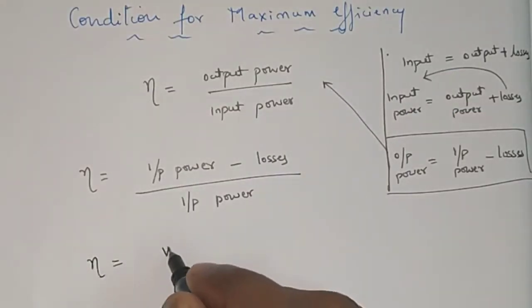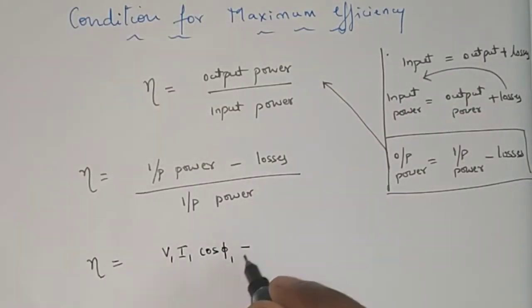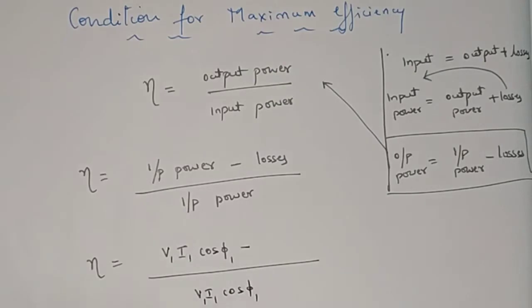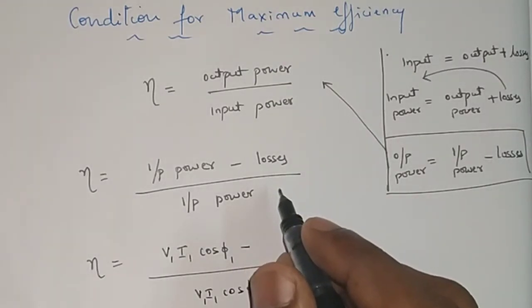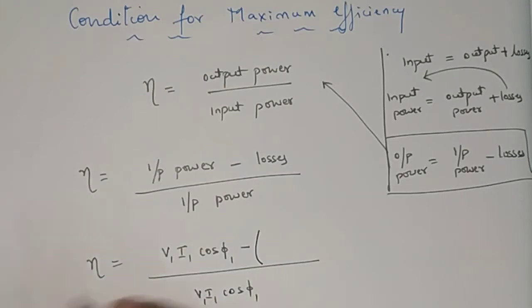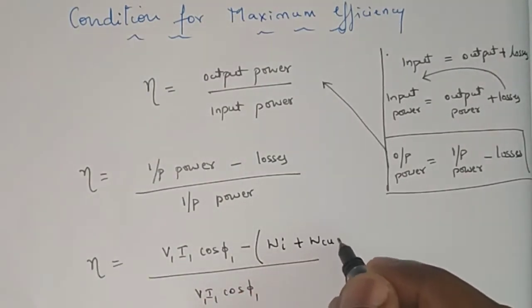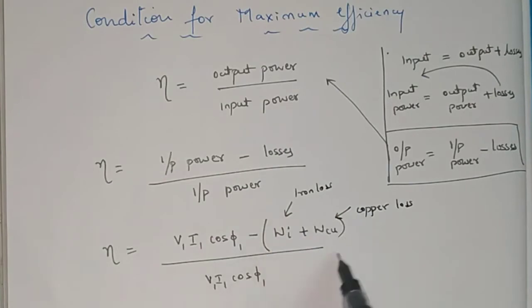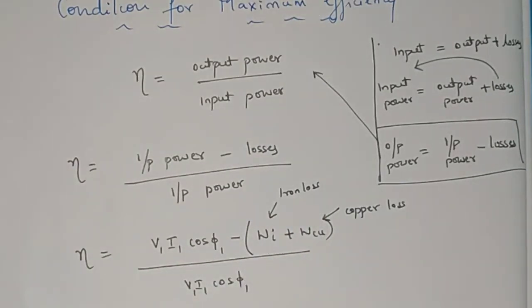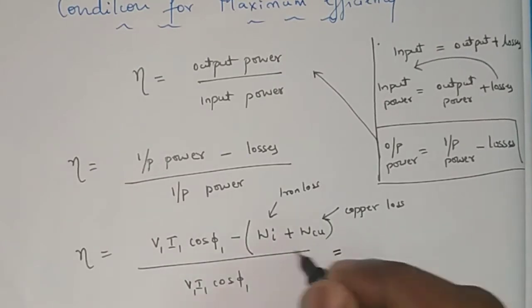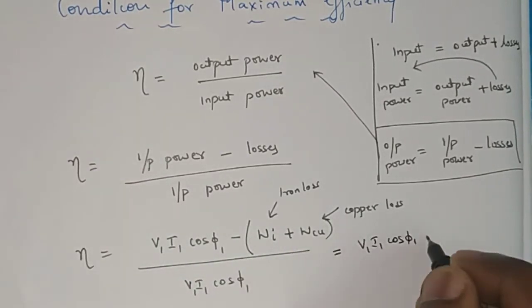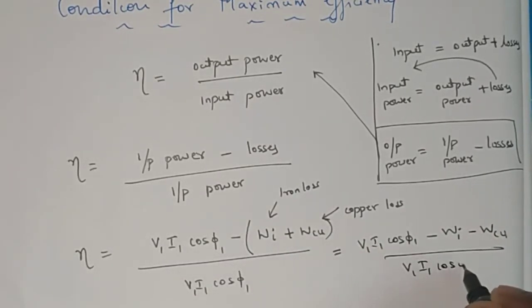So eta is equal to V1·I1·cos φ1 minus losses in the numerator, divided by V1·I1·cos φ1 in the denominator. Now, what are the losses in the transformer? We know the total losses in a transformer are iron loss plus copper loss. I will represent Wi as iron loss and Wcu as copper loss. So total losses are iron loss plus copper loss. Multiplying the negative sign inside the bracket and simplifying, I will get V1·I1·cos φ1 minus iron loss minus copper loss, divided by V1·I1·cos φ1.